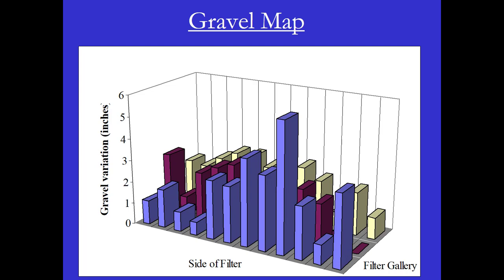Here's a gravel map. It shows that the gravel in this filter is not that even — there is a difference of about five inches. It's not too bad, but it does show that there's an unevenness of the gravel.